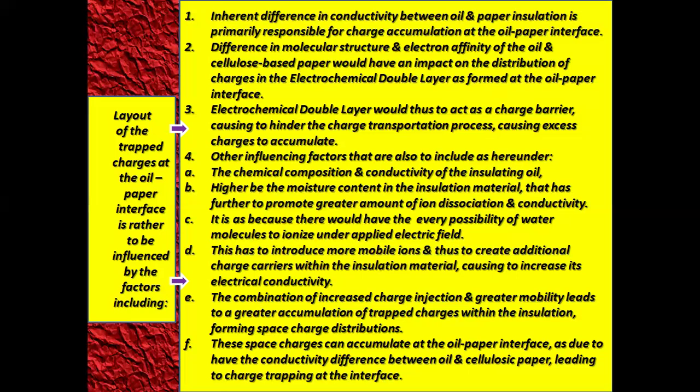The combination of increased charge injection and greater mobility leads to a greater accumulation of trapped charges within the insulation, forming a space charge distribution. These space charges can accumulate at the oil paper interface due to the conductivity difference between oil and cellulosic paper, leading to charge trapping at their interface.